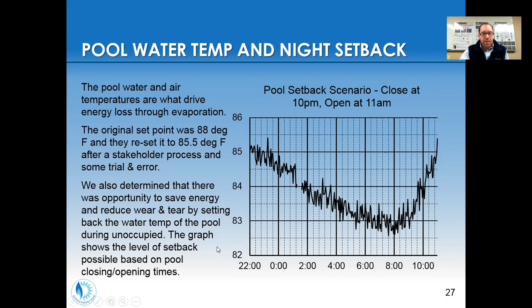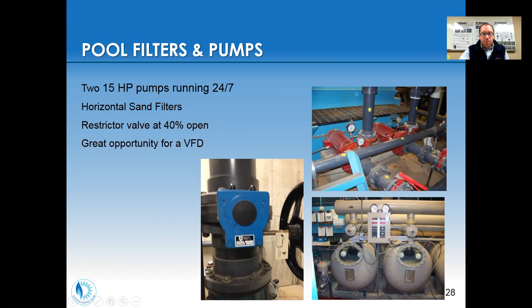For pool filters and pumps, in this case we have 2 15 horsepower pumps and 2 15 horsepower motors, and they're running 24/7. So really just a lot of energy use going into the circulation pumps. They're going through horizontal sand filters. Now in this picture you see this giant crank and this butterfly valve, and it's labeled here with a little Sharpie marker as 30% or 40% open. So in this case, this pool is restricting the flow of their recirculation water.